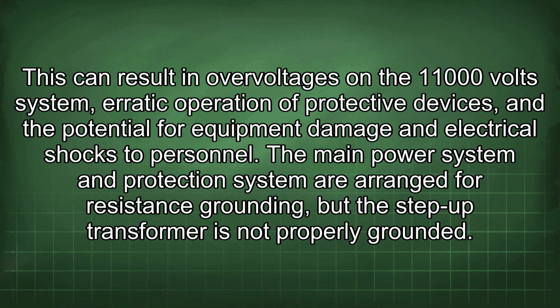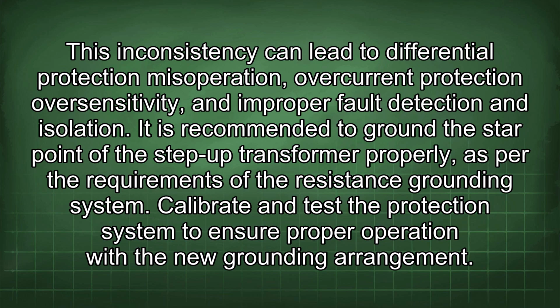The main power system and protection system are arranged for resistance grounding, but the step-up transformer is not properly grounded. This inconsistency can lead to differential protection misoperation, overcurrent protection oversensitivity, and improper fault detection and isolation. It is recommended to ground the star point of the step-up transformer properly, as per the requirements of the resistance grounding system. Calibrate and test the protection system to ensure proper operation with the new grounding arrangement.